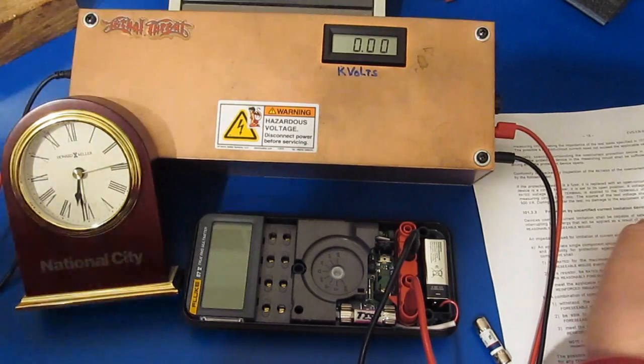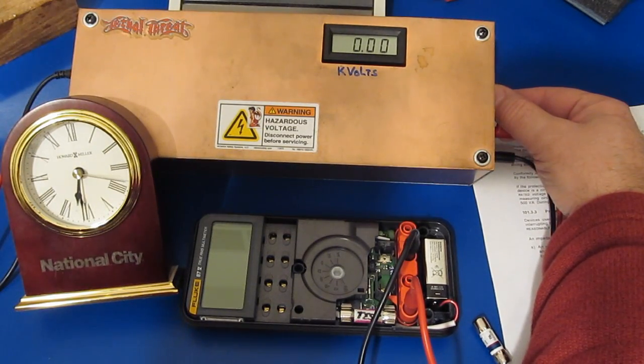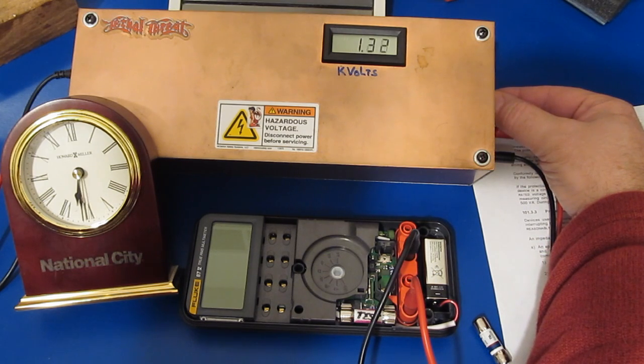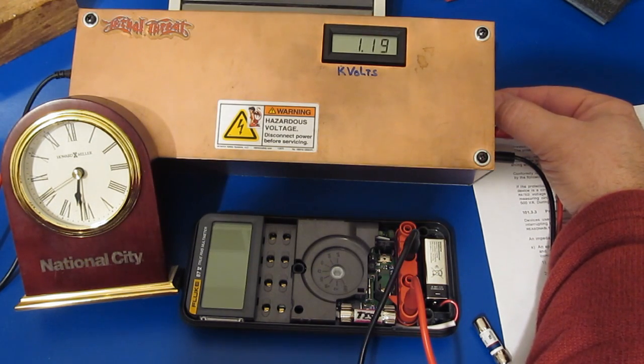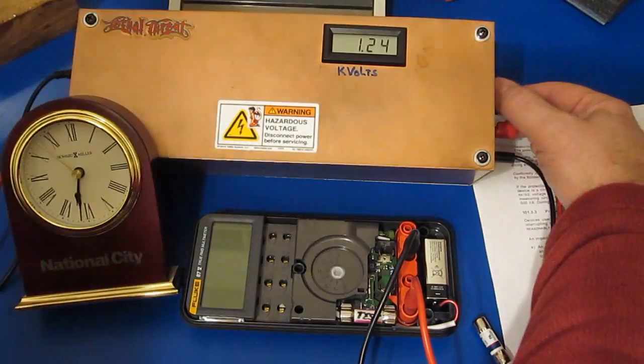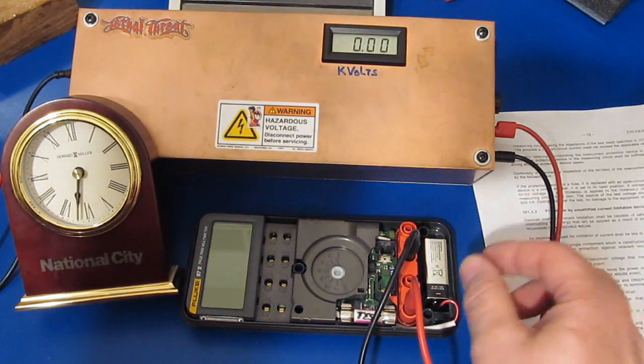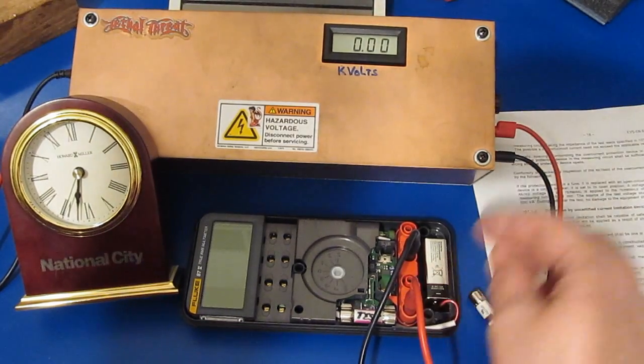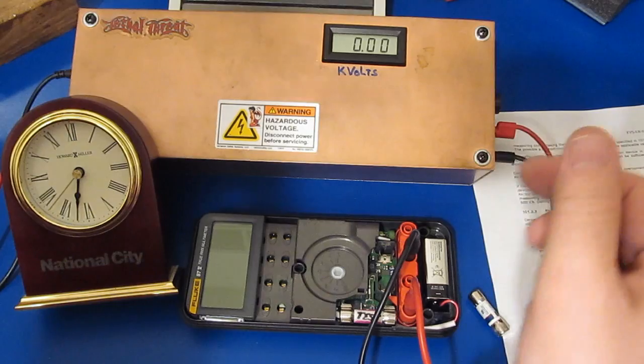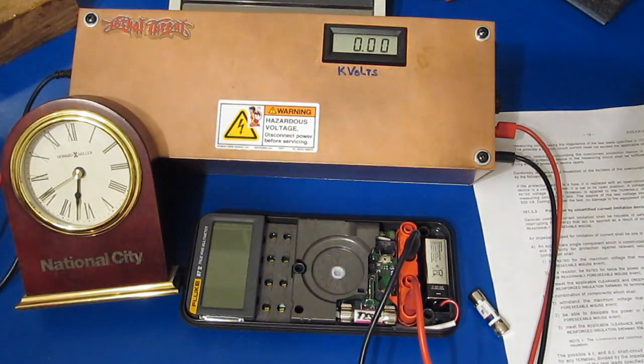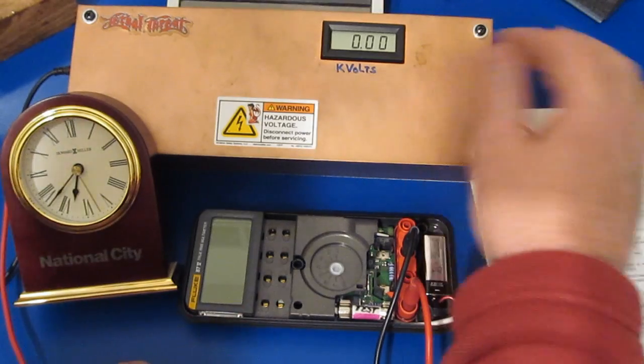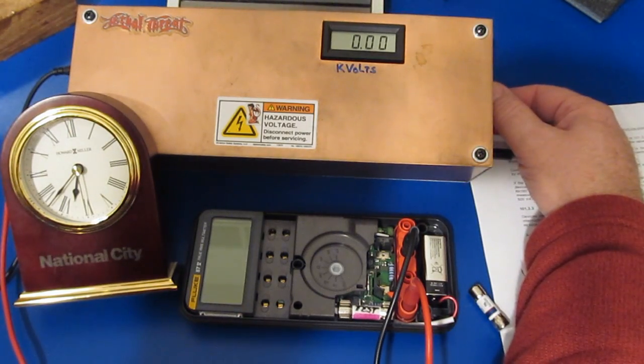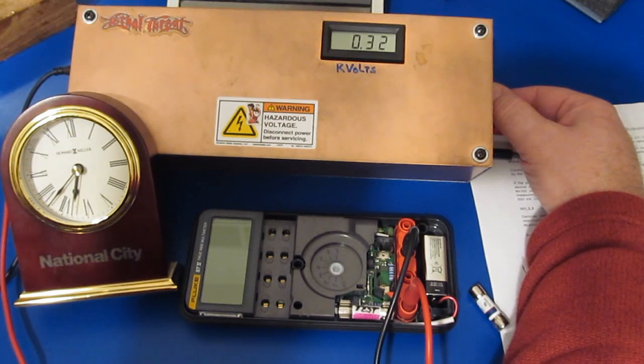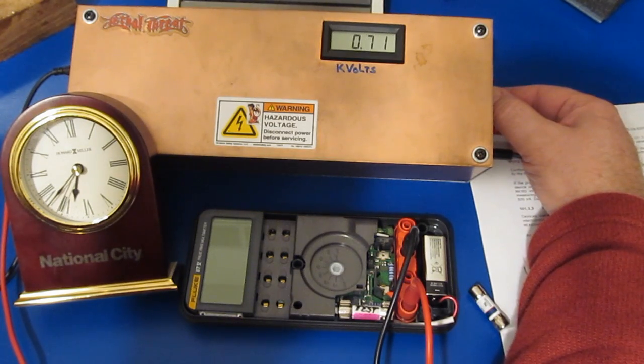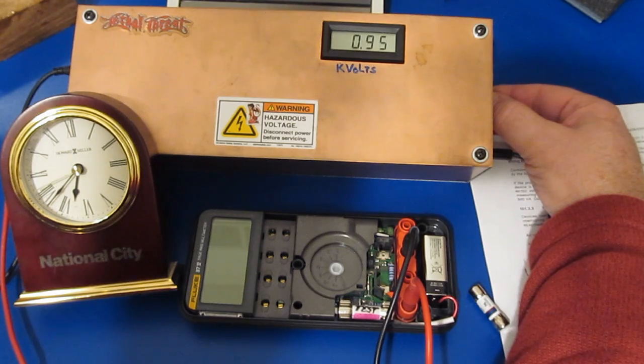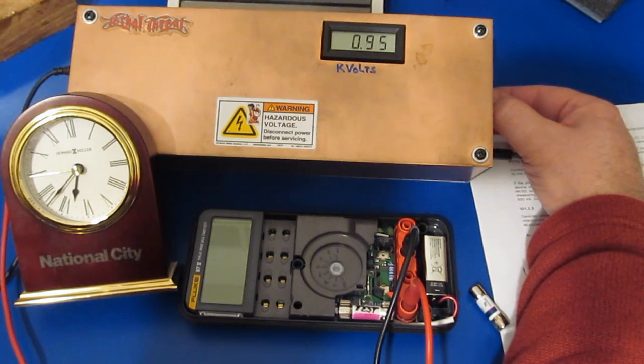We're going to be applying a 2000 volt signal. I think what's happening is the circuitry used to detect if the leads are in the right position is actually clamping this input voltage. Whatever's dragging this power supply down, I can't overcome it. So the best we're going to be able to do, it looks like, is to test it at about 1.36 kV or so. Let's see where it folds over, right about there, so about 1.3 kV.